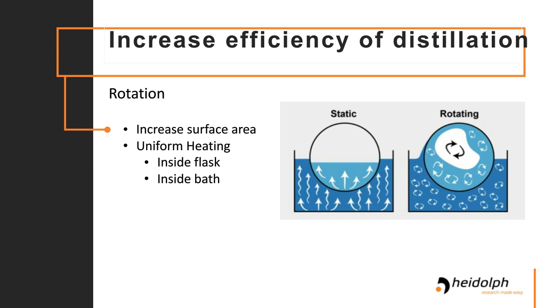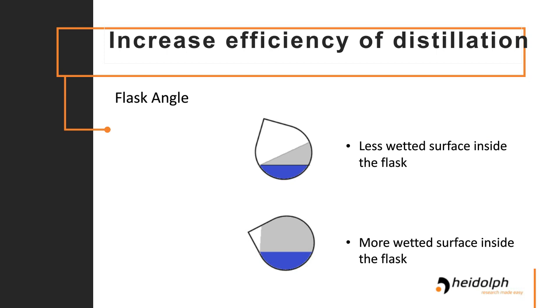Another thing to consider with your evaporating flask is the angle that you have it sitting in the bath. If you have it at too pitched of an angle, you'll notice that as it's rotating, you're not using the entirety of your flask. There's less wetted surface inside of it, and it's not all evaporating at the same time. When you have it at a lesser angle, closer to 180 degrees, you'll see that the rotation is pulling the liquid all the way around the evaporating flask, leading to increased surface area, which means more can evaporate at the same time.